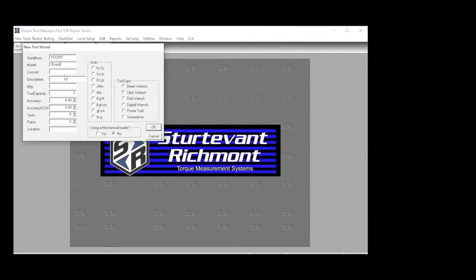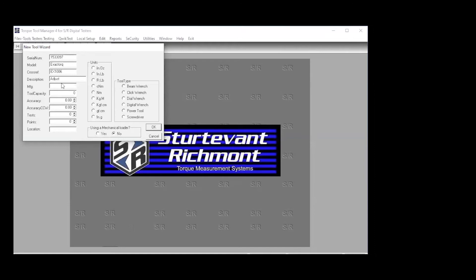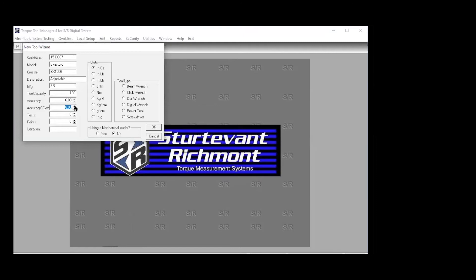In this particular case, it starts with the serial number, and we're going to go through this real quickly. This is 7533097. This is an exact torque. It's a cross-reference number. Description, this is an adjustable torque screwdriver. The manufacturer is Sturtevant Richmont. This happens to be a 100 inch ounce. Click your units to measure. Torque screwdrivers are plus or minus 6%. This one works in both directions. So we put that in there. We're going to give this test five tests. And we're going to test it at three points. And it is a torque screwdriver. We need to put that in there. And we've gone ahead and we do that.